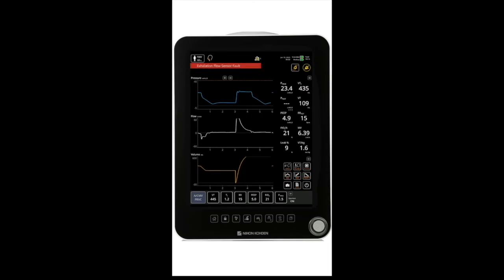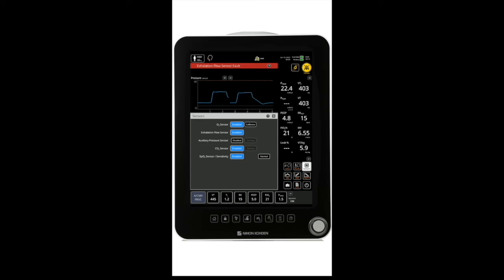During clinical use, the clinician can switch out the expiratory flow sensor without interrupting ventilation. You can silence the alarm and quickly switch out, or I can go to my apps and select my sensors, and I can disable my expiratory flow sensor if I need a little more time.